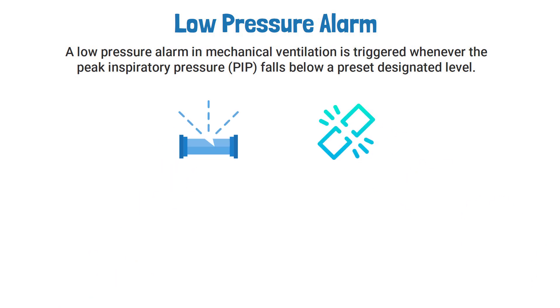A low pressure alarm in mechanical ventilation is triggered whenever the peak inspiratory pressure falls below a preset designated level. This most commonly occurs whenever there is a leak or disconnection in the system.